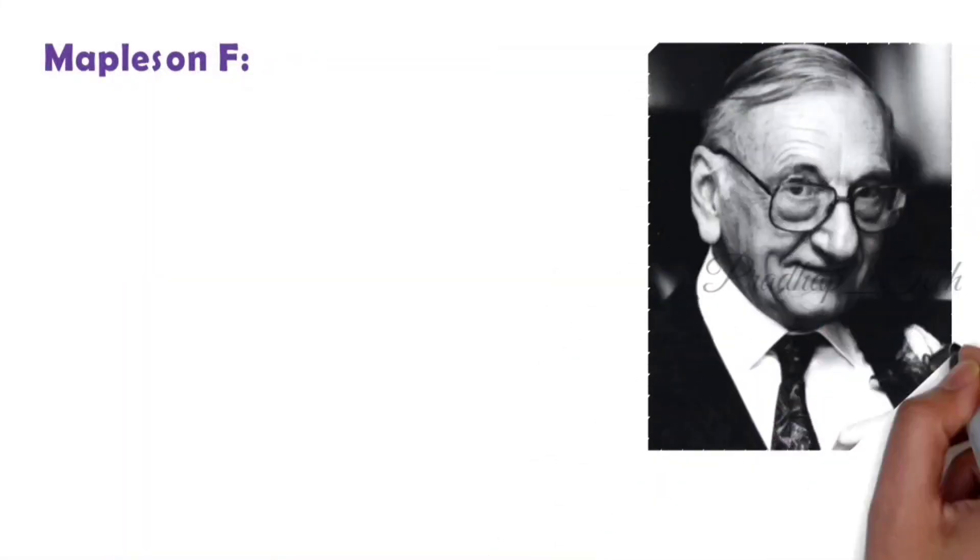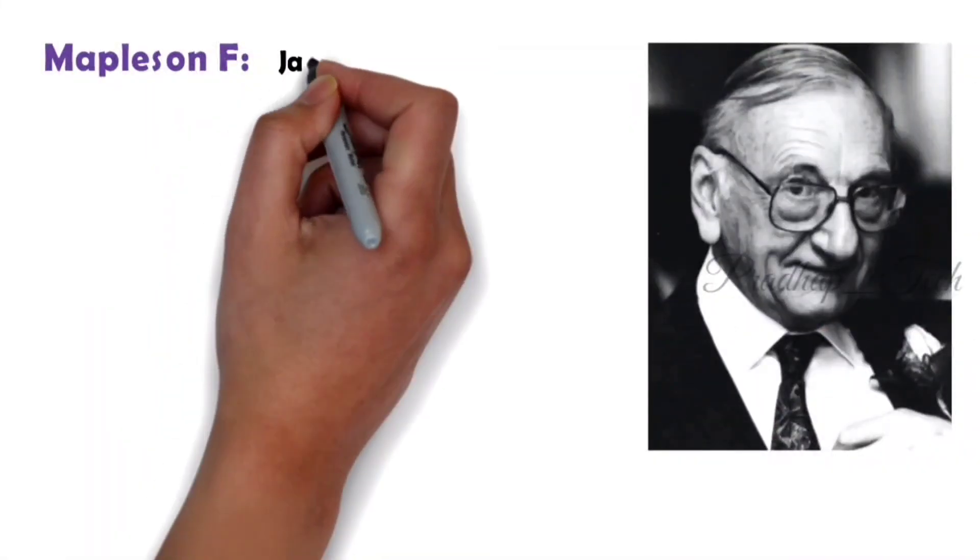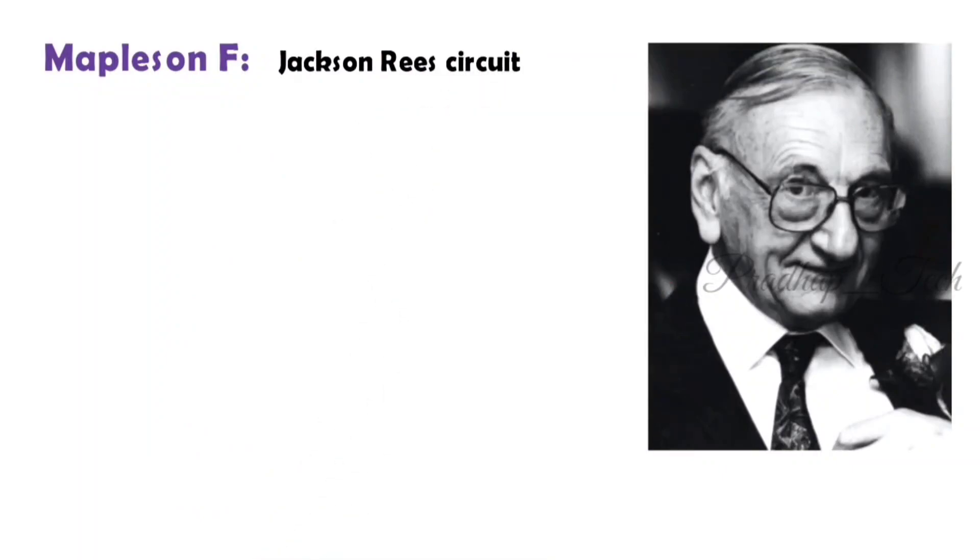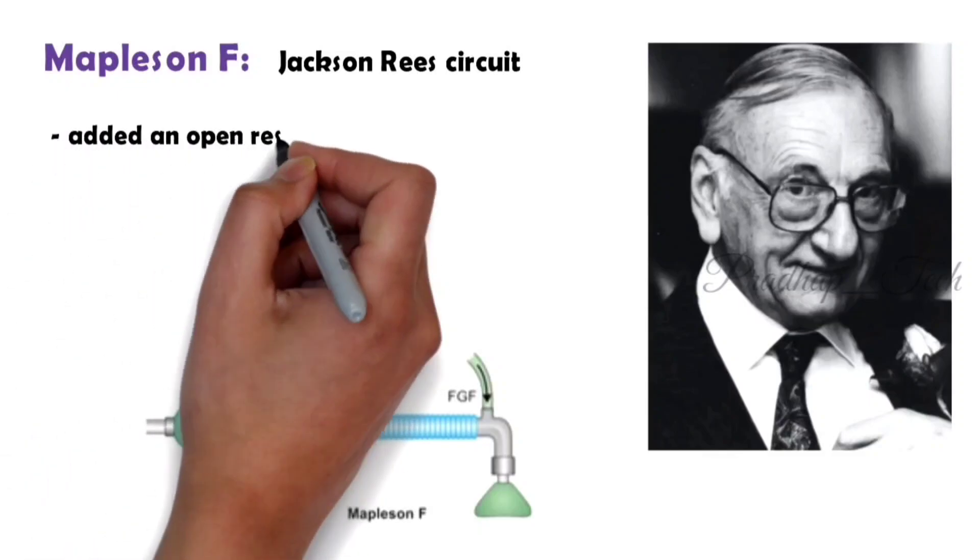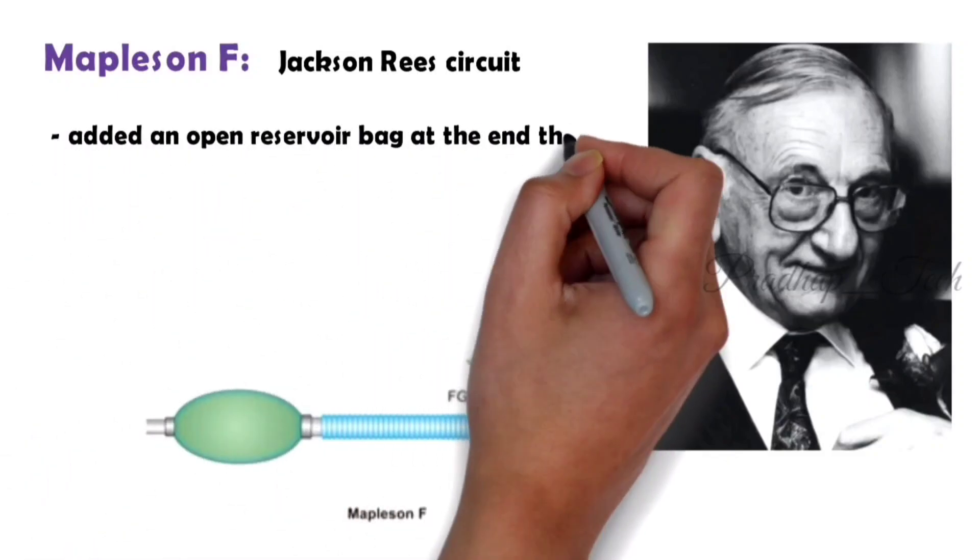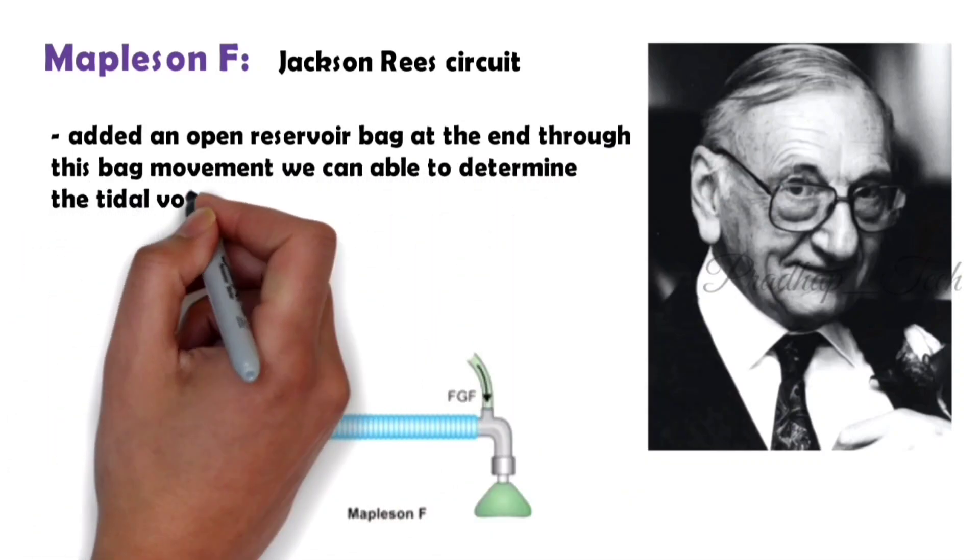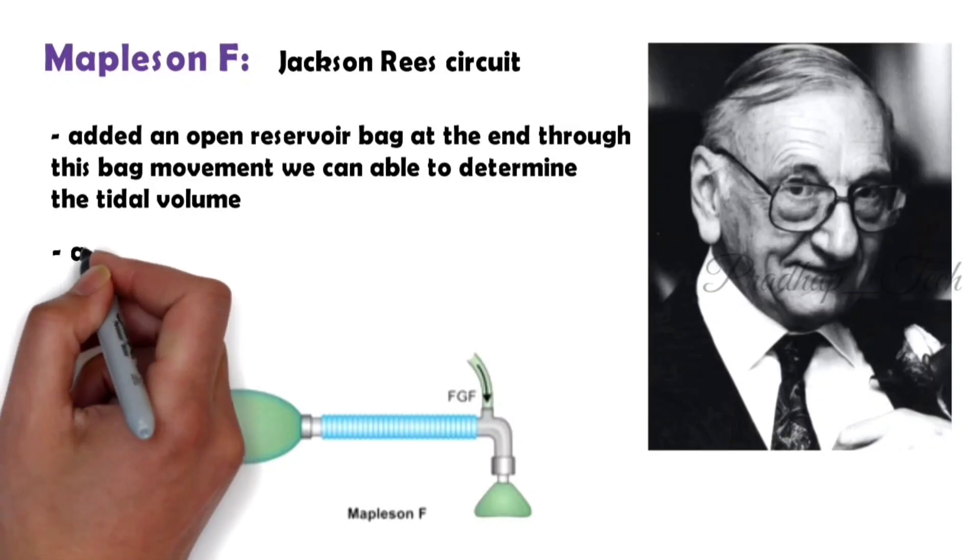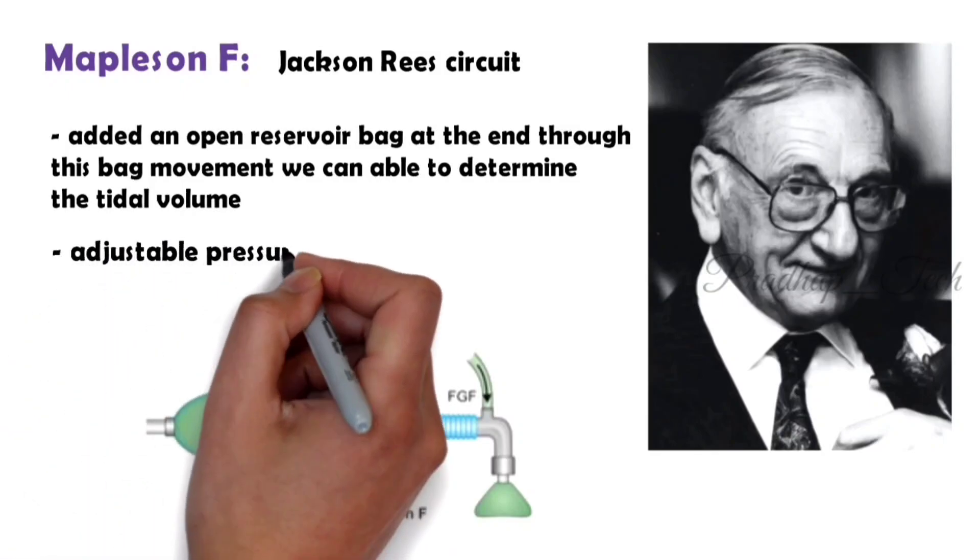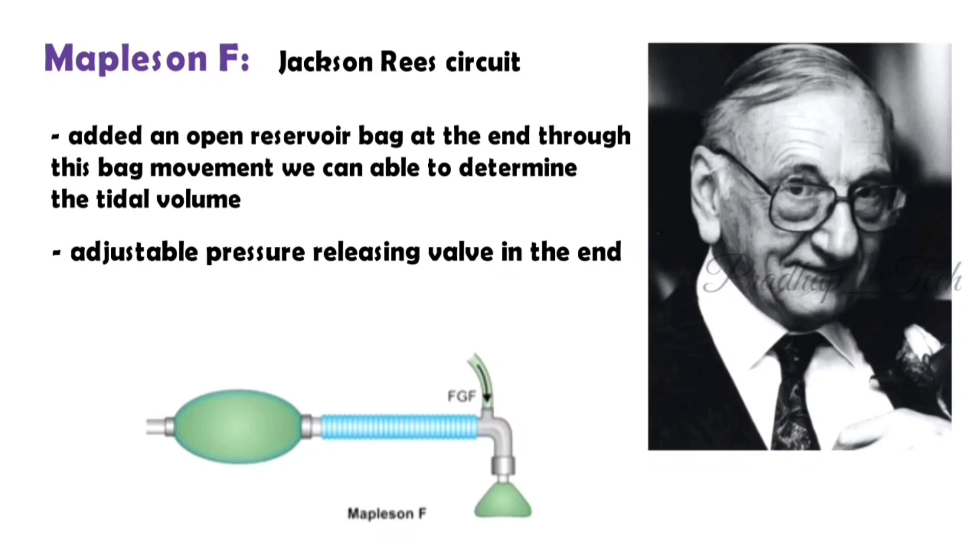Mapleson F: this circuit was found by Jackson-Rees, so it is also known as the Jackson-Rees circuit. It is a modification of Ayre's T-piece. He added an open reservoir bag at the end; through this bag movement we can determine the tidal volume. There's an adjustable pressure releasing valve in the end. By using that valve, this circuit can be used for both spontaneous and controlled ventilation.